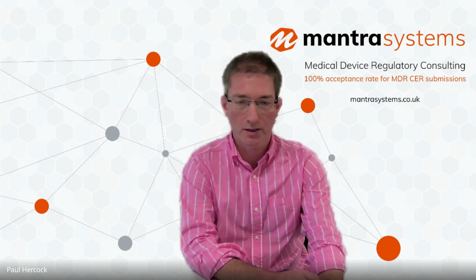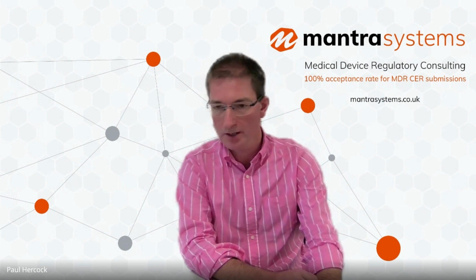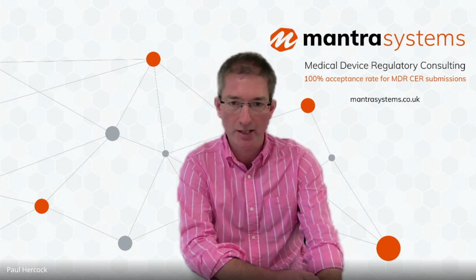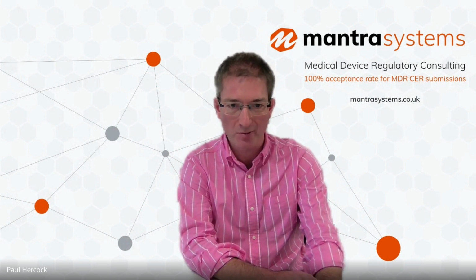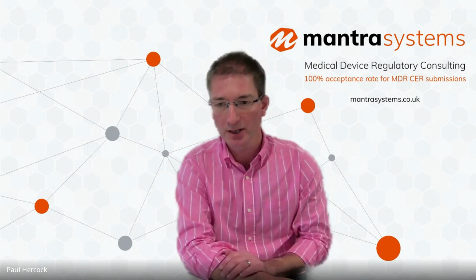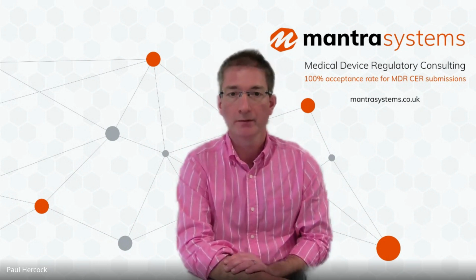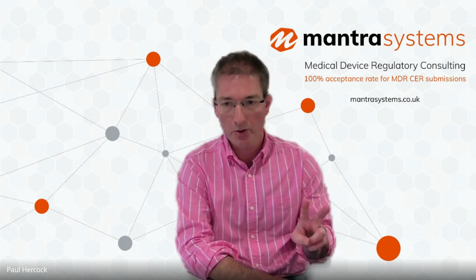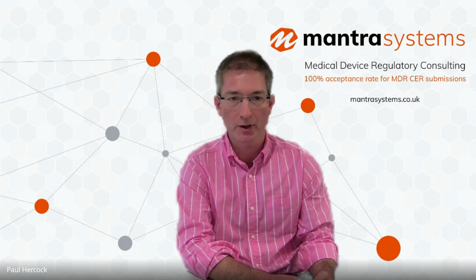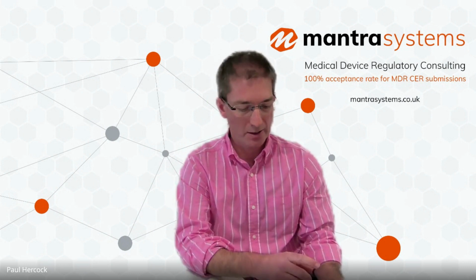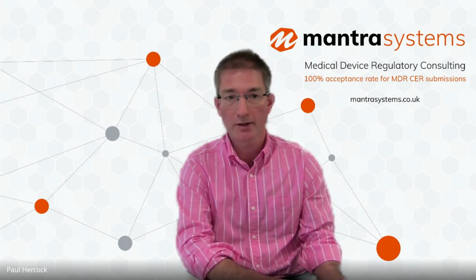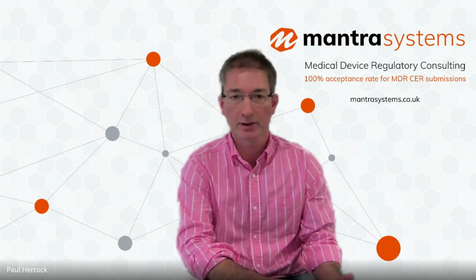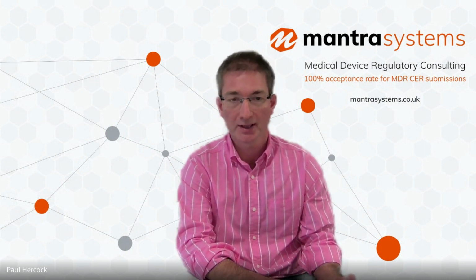Do you follow that? So I think the question is, essentially, can you use state-of-the-art data to demonstrate conformity of the subject device? If that is the question, the answer is no. There's only two sources of evidence that can demonstrate conformity. That's clinical evidence on the subject device itself or clinical evidence on an equivalent device.